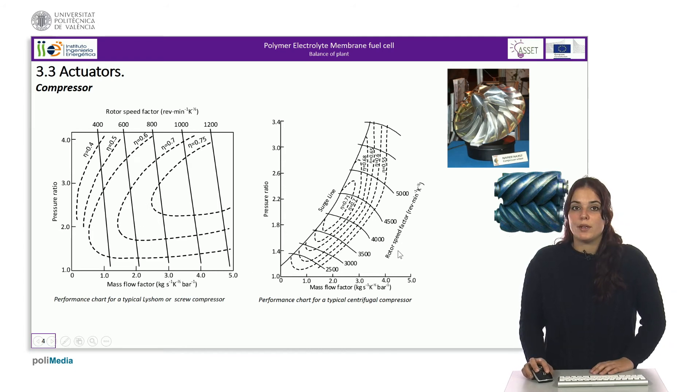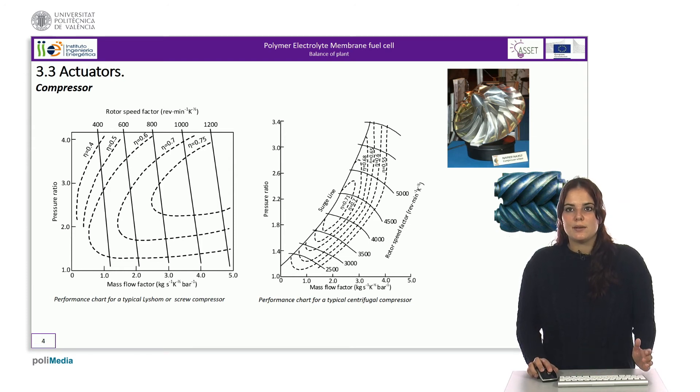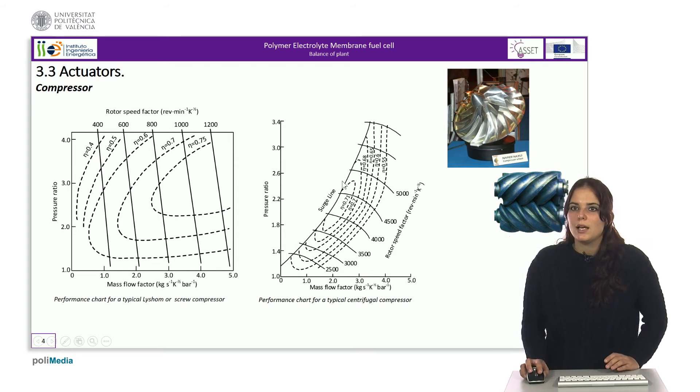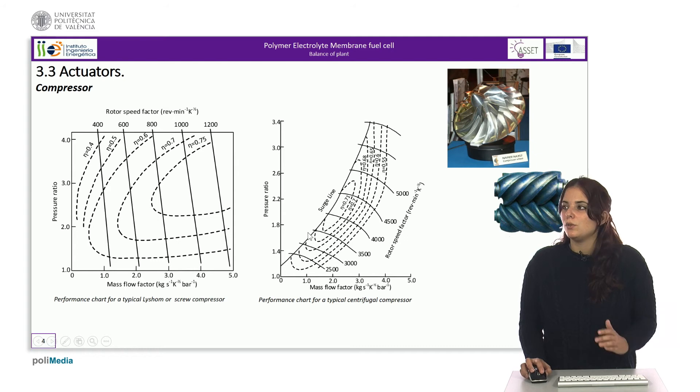The graph on the right shows the operating curve of a centrifugal compressor. Unlike the Lysholm, this compressor has a zone of instability above the surge line, so these are operating points that should not occur.